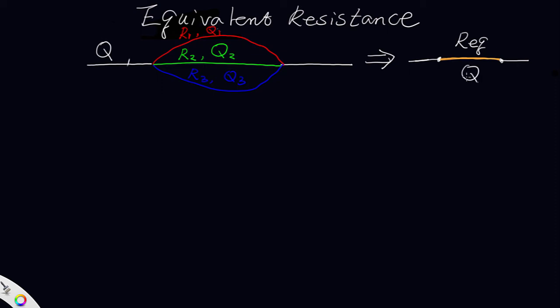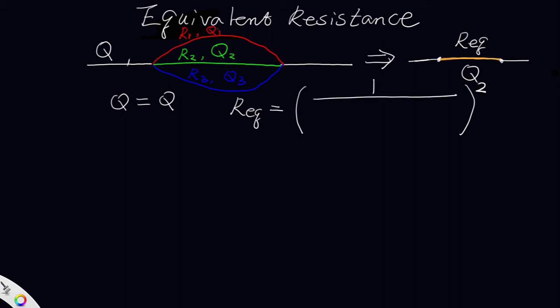In this scenario, the total airflow going to the three airways in parallel is the same as the total airflow going into the equivalent airway, so Q remains unchanged. To calculate the equivalent resistance, we have this equation: R-equivalent equals the square of 1 divided by the sum of (1 divided by square root of R1) plus (1 divided by square root of R2) plus (1 divided by square root of R3).